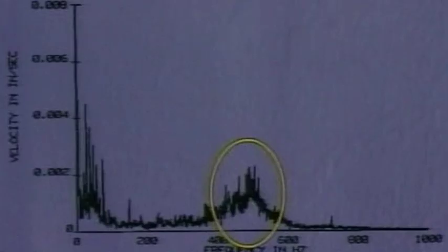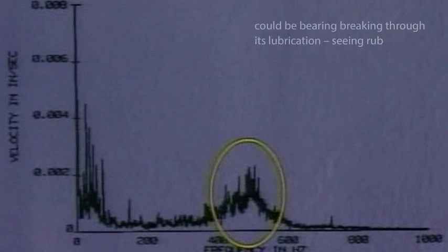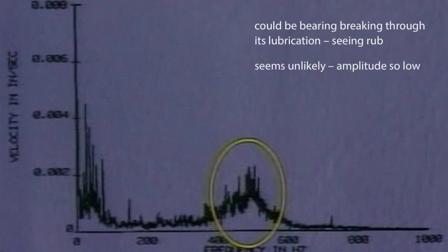We also find a family of peaks around 500 Hz. Now, there are a couple of things this could be. First, it could be that the bearing is breaking through its lubrication, and we are seeing rub. This seems unlikely, however, because the amplitude is so low. Second, this pattern is often associated with pump cavitation.